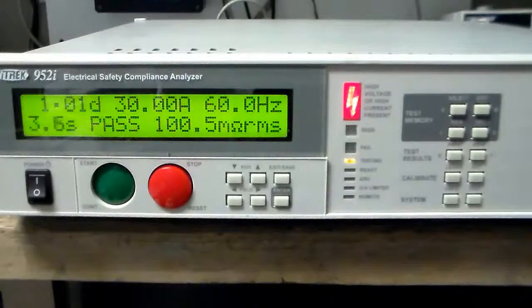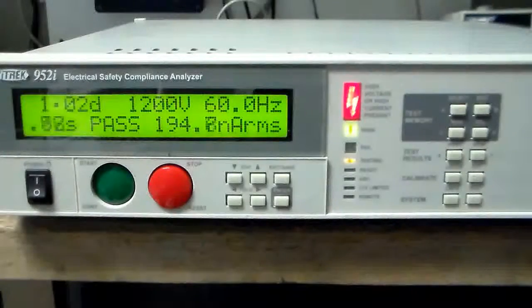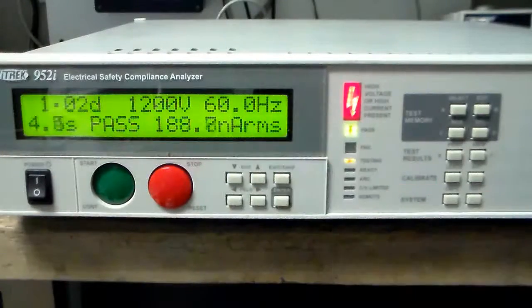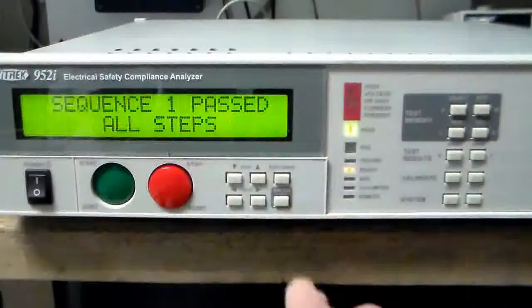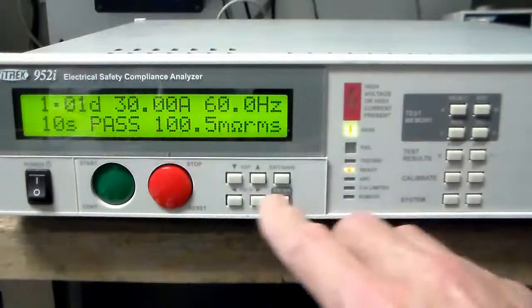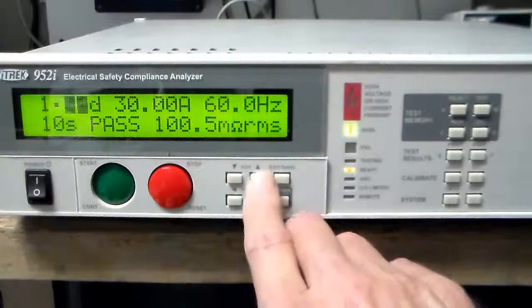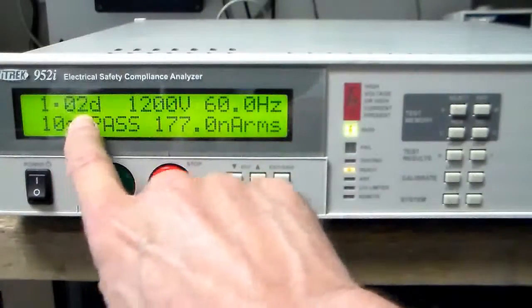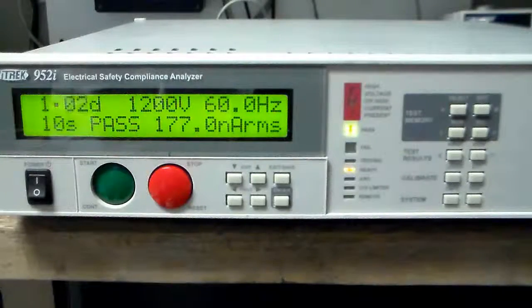The test is running right now. I have it hooked up to a 100 milli-ohm lead, and you can see it's reading 100.5 milli-ohms. Then it does the high pot test, and we have virtually no leakage at all — it's in the nano-amps. When it's finished, it displays the last values. Step one came to 100.5 milli-ohms, and if you press the up button, it goes to step two, showing 177.0 nano-amps — so it tells you the result of what you're doing.